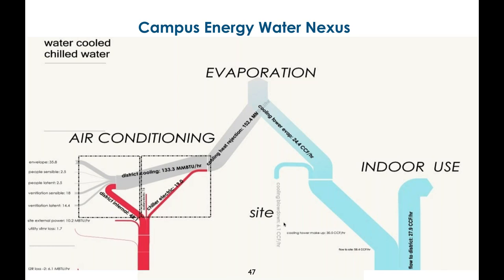Ultimately, those two combine, we talked about that, and we dissipate it through the cooling tower. On the blue side, you're seeing a little line there, kind of a U-shaped line draining down. That's the blowdown. So if you hit the button here, two key parameters in this: the coefficient of performance, how efficient your chiller plant is, gives you an idea of the ratio of how much electric energy it takes to pull the rest of the heat out of this thing.